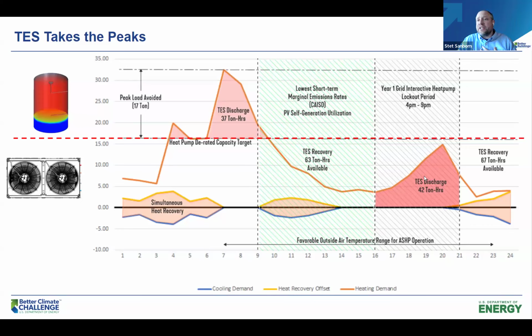In the case of this project, we also wanted to actually shut off our heat pumps completely from 4 to 9 p.m. because in California, that's where we pay through the nose for electricity. And so we sized this tank to not only handle that morning warm up, but also to be able to turn off our heat pumps completely in the afternoon and just ride the tank out until 9 p.m. And then we could turn the heat pumps back on, recharge the tank, and be ready in the morning.